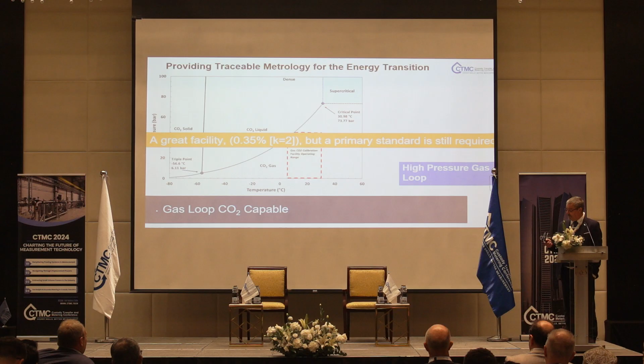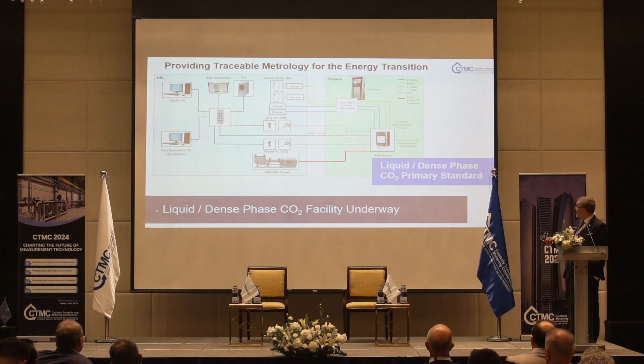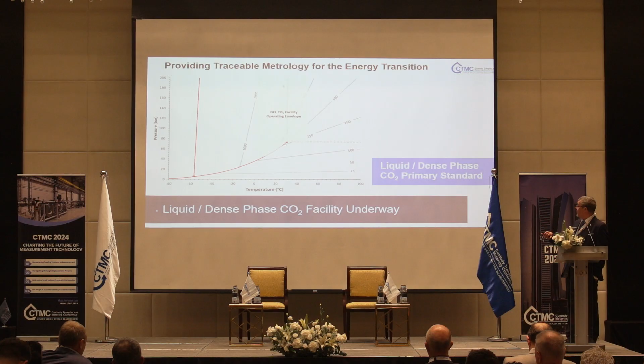In terms of the liquid and dense phase CO2, we're making great progress at NEL. We're building a primary standard based around a compact prover. We'll be able to bring meters in and, using mass and time, calibrate them. So we will have a primary standard. I was going to say 2025, but 2025 is actually pretty close now. Maybe mid-2025, not quite sure. And again, we think that will be useful because here the operating envelope has been chosen to overlap the dense phase pipeline and possibly some of the sequestration conditions that will occur during the final stages of pushing the carbon dioxide back underground. That is a primary standard.